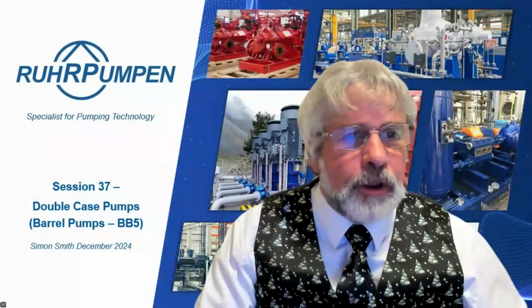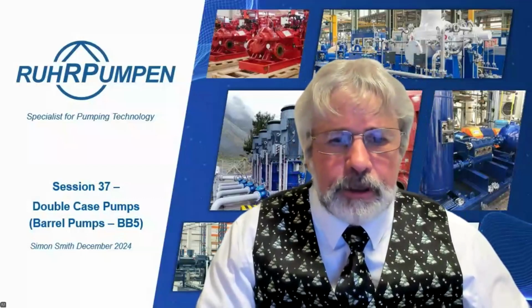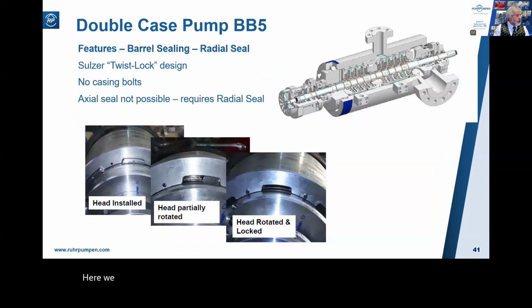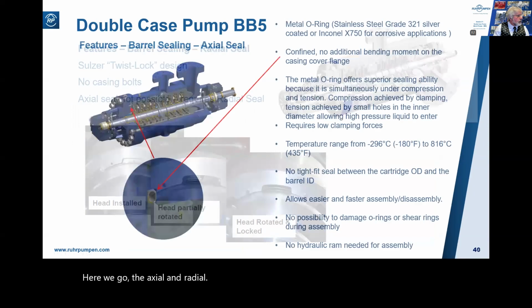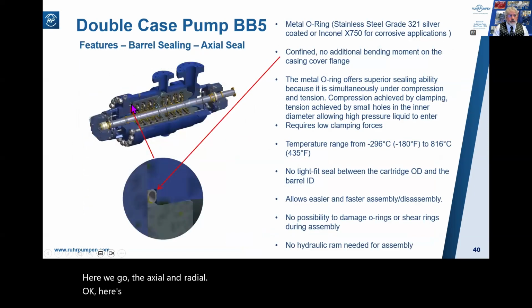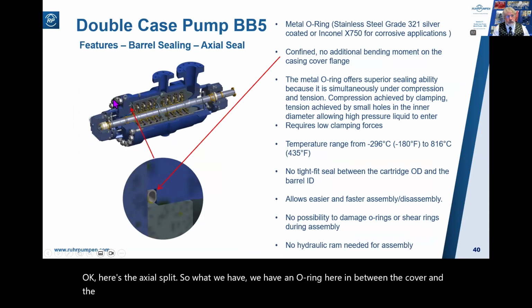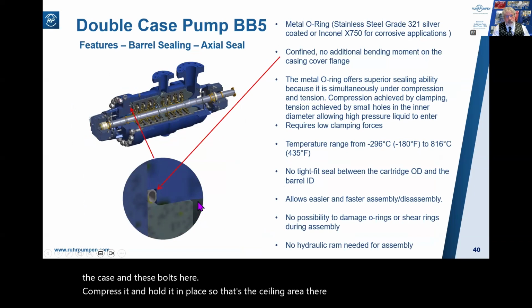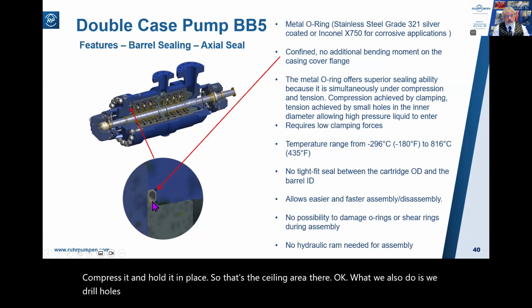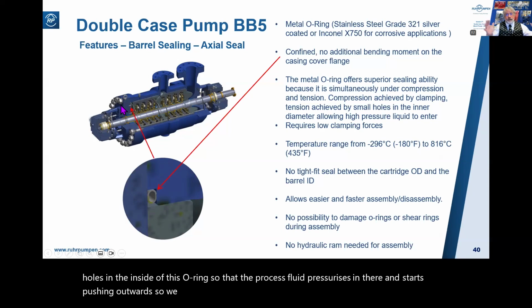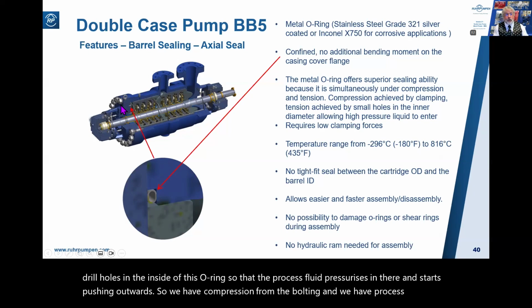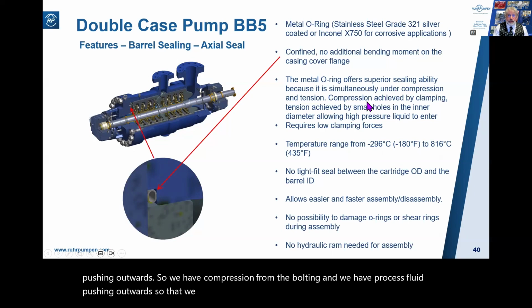Okay. I still have 60 of you online. Let me see if I can go back, and here we go. The axial and radial split. Okay, here's the axial split. So what we have is an O-ring here in between the cover and the case, and these bolts here compress it and hold it in place. So that's the sealing area there. What we also do is drill holes in the inside of this O-ring so that the process fluid pressurizes in there and starts pushing outwards. So we have compression from the bolting and we have process fluid pushing outwards, so that it is simultaneously under compression and tension and therefore requires low clamping forces.